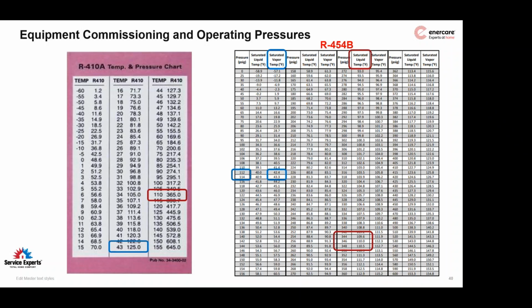And then when it comes to pressures specifically, 43-degree refrigerant temperature, not unusual for R410A, 125 psig, completely normal.